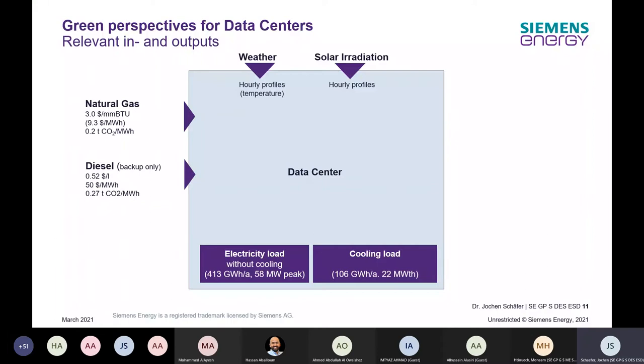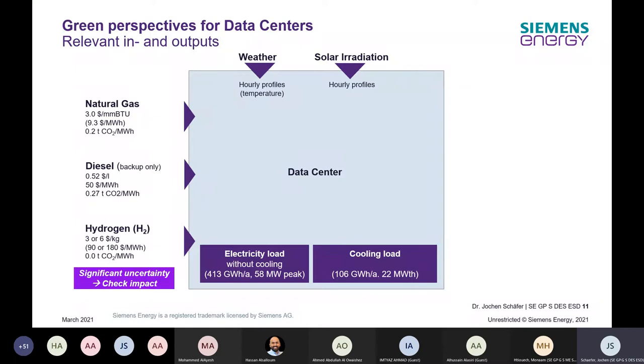We have the option of using diesel as a backup fuel, and we take into consideration hydrogen as a fuel with zero carbon intensity. However, discussing with the customer, we had intensive discussions on the hydrogen price and realized there's significant uncertainty about the future hydrogen price. We agreed to run two cases: one at three dollars per kilogram and one at six dollars per kilogram, and we'll examine the impact on cost and system configuration.